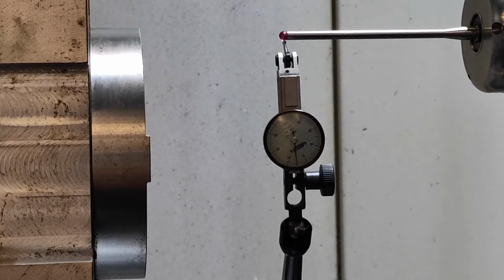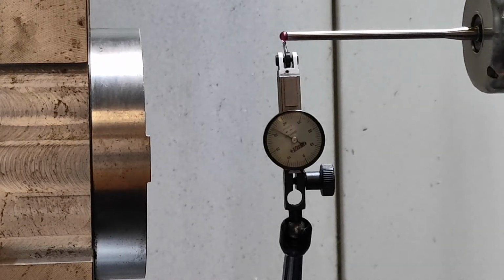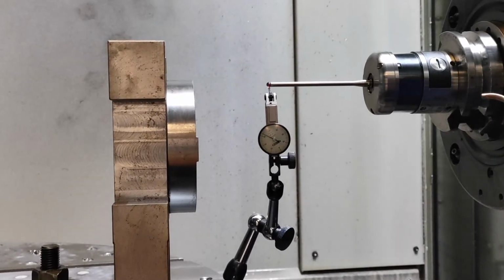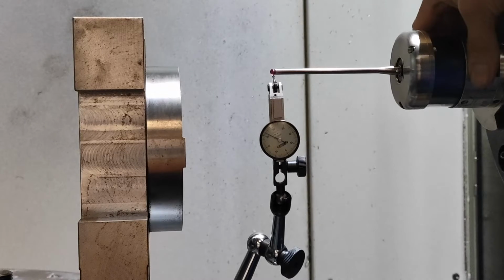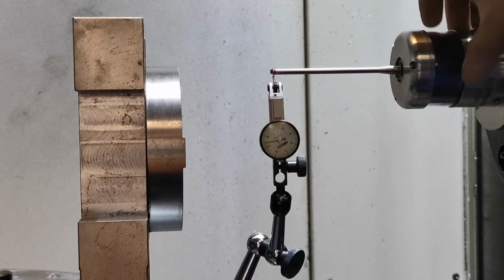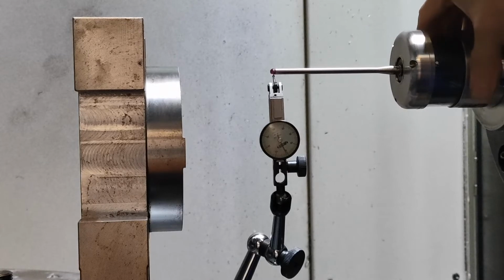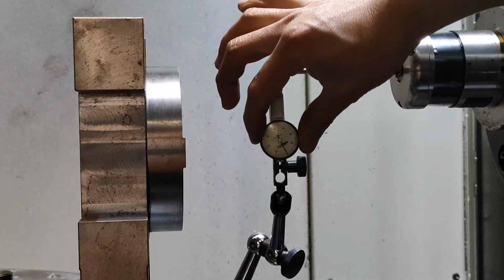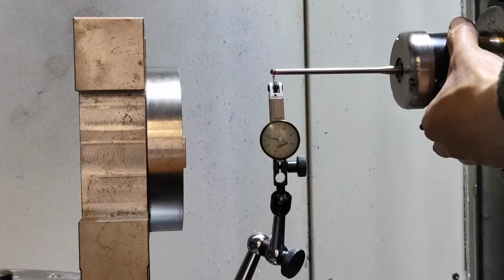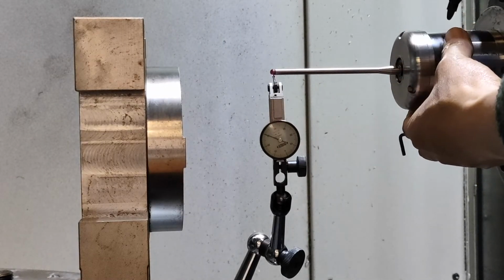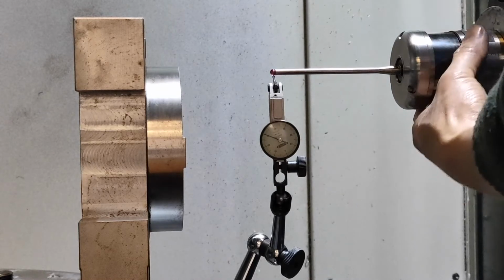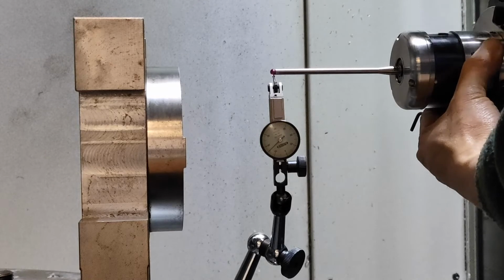point of the stylus. Once I get the highest point of the stylus, I am going to rotate it so that I can see how big the run out of my probe is. So looks like it is roughly 0.35 millimeter. I will zero it again and I will put a number at the same position of each screw on my probe so that it is easy for me to adjust.